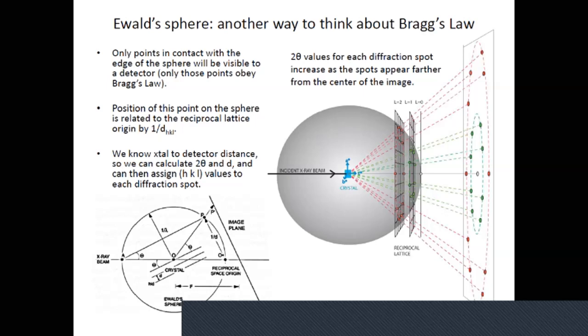If you know the crystal-to-detector distance — typically about 35 mm for small molecules — you can calculate 2-theta and the d-spacing. Combined with the crystal's known orientation (set by machine parameters), you can calculate HKL values for each diffraction spot. This is how the HKL values are constructed, as we practiced in the HKL homework.